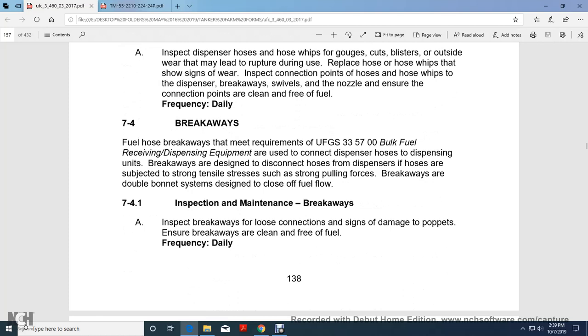7.4 Breakaways. Fuel hose breakaways meet the requirements of Unified Facilities Guide Specification 33 57 00, bulk fuel receiving and dispensing equipment, and are used to connect dispenser hoses to dispensing units. A breakaway is designed to disconnect the hose from the dispenser if the dispenser and hose are subject to strong tensile forces such as strong pulling forces. Breakaways have a double poppet system designed to close and shut off fuel flow.